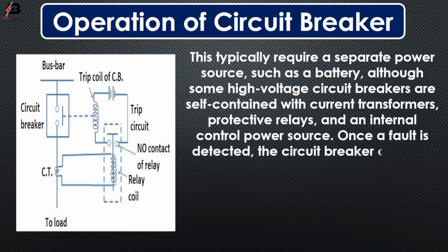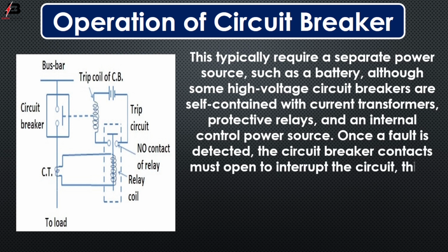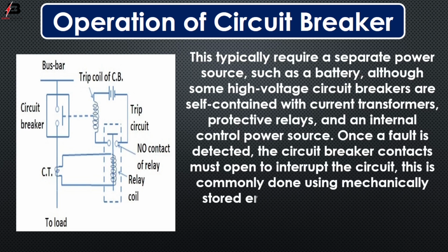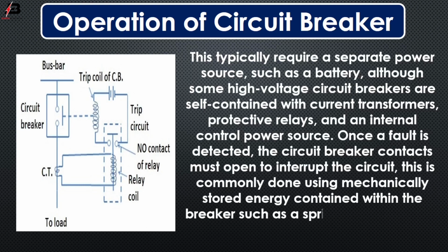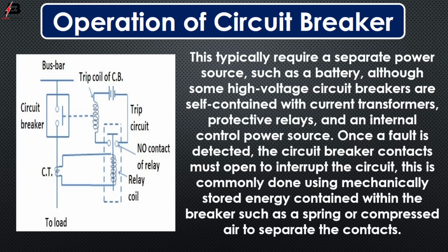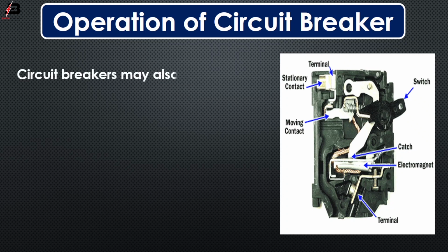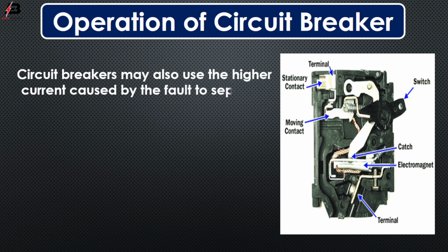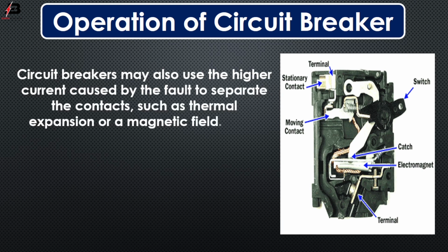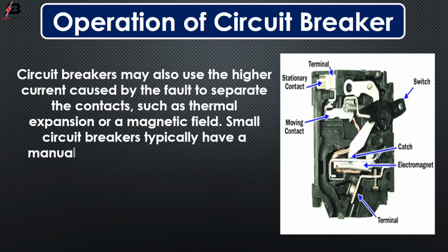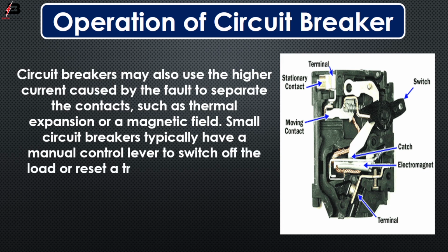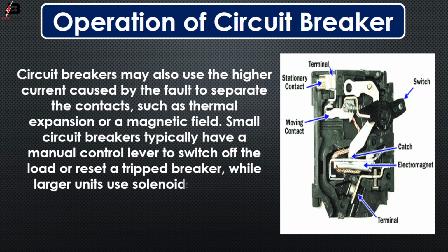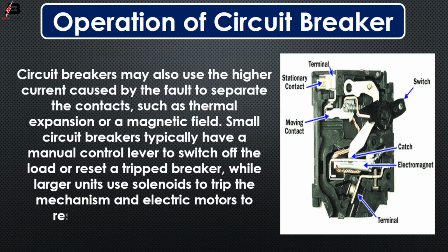Once a fault is detected, the circuit breaker contacts must open to interrupt the circuit. This is commonly done using mechanically stored energy contained within the breaker, such as a spring or compressed air, to separate the contacts. Circuit breakers may also use the higher current caused by the fault to separate the contacts, such as thermal expansion or a magnetic field. Small circuit breakers typically have a manual control lever to switch off the load or reset a tripped breaker, while large units use a solenoid to trip the mechanism and electric motors to restore energy to the springs.